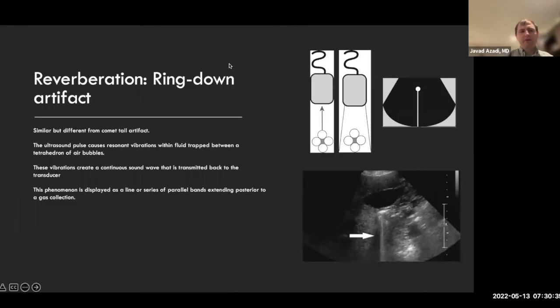Another reverberation artifact is ring down. It's similar but different. The ultrasound pulse resonates within fluid trapped between air bubbles, and these vibrations cause a continuous sound wave that is transmitted back. So instead of equidistant lines, it's a kind of sound wave that just goes all the way to the bottom. This is helpful to determine if there's fluid or gas in a collection. It can contribute to dirty shadowing.